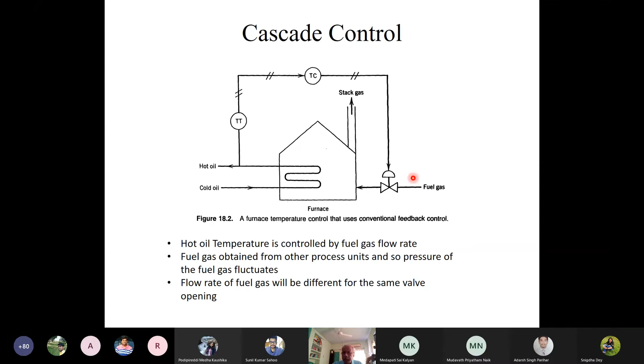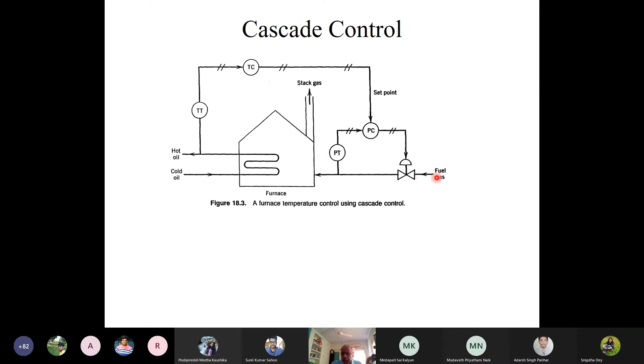So the question comes, how to take care of it? Here basically hot oil temperature is controlled by the fuel gas flow rate. Fuel gas, as I told earlier, is obtained from other process units, and so the pressure of the fuel gas fluctuates, and the flow rate of fuel gas will be different for the same valve opening. So how to take care of this? We can take care of this by setting that, irrespective of the fuel gas header pressure fluctuations, the flow rate of the fuel gas should remain constant for a specific controller output. For a specific controller output TC, the flow rate of the fuel gas should remain constant irrespective of the fuel gas header pressure fluctuation.